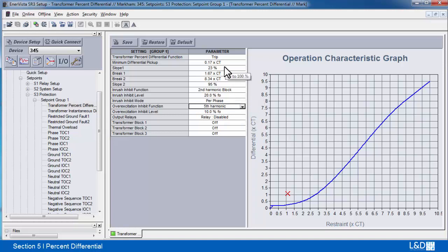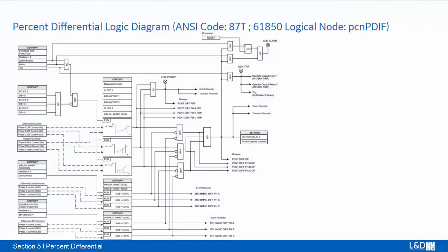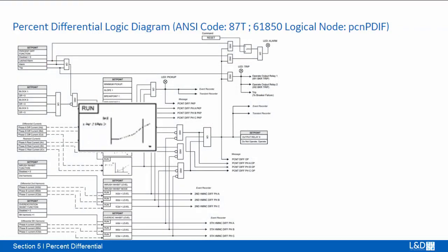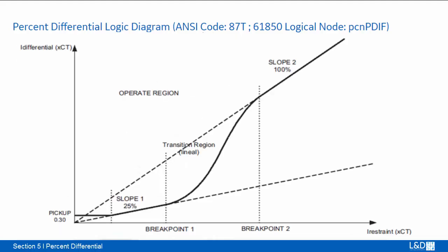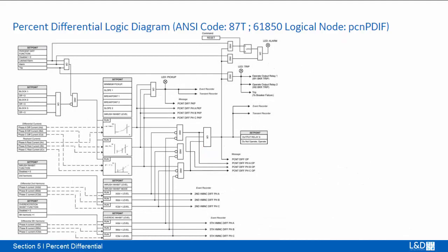Once these settings are entered, the characteristic can be plotted on the right side of the screen, so we can see the theoretical slope, with slope 1 and 2 and also breakpoint 1 and 2. In the logic diagram, the phase operation is based on slope: when the actual slope is greater than the setting slope, the relay will operate. This percent differential is blocked by the second harmonic and fifth harmonic.